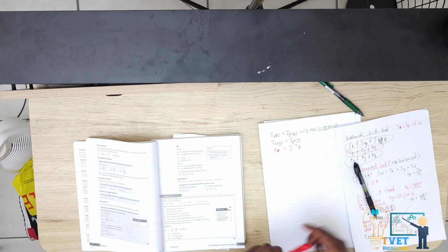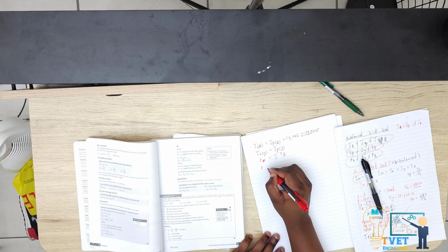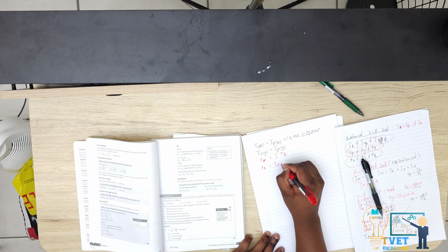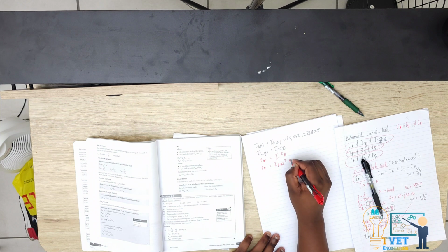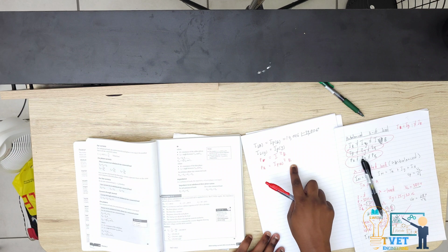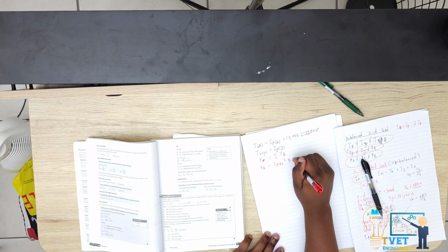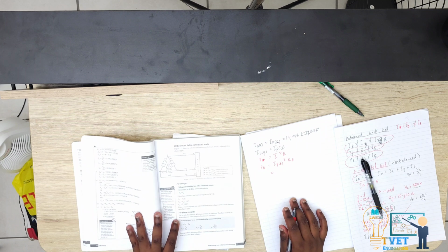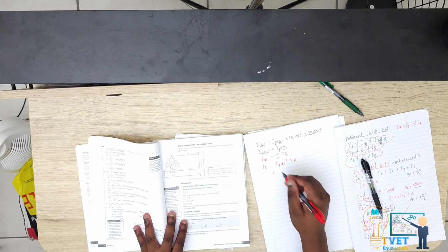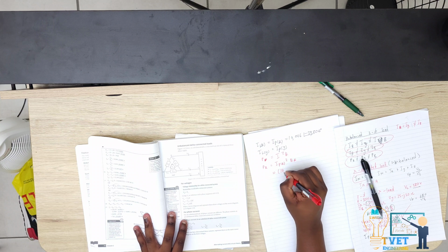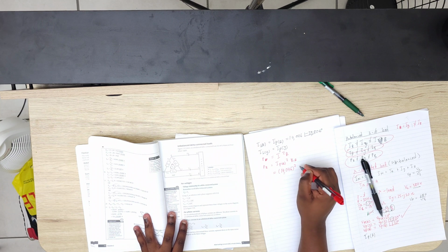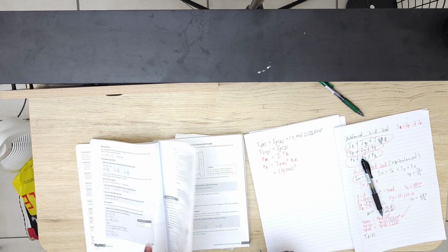So if I'm going to use this formula, the power of the red phase is the current of the red phase squared, times the resistance of the red phase. The current of the red phase, which we calculated as 14.046, squared. For the resistance, you go to the impedance.